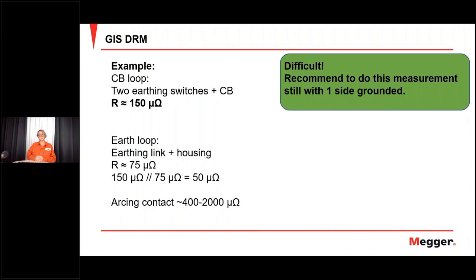I talked about the resistance earlier in the circuit, that it was trouble with GIS because you have a grounding circuit which has a very low resistance. And because of that, I would still recommend to do DRM with one side grounded. And I hope we're going to be able to help and do a better solution for that, but it is difficult to do GIS dual ground on DRM.